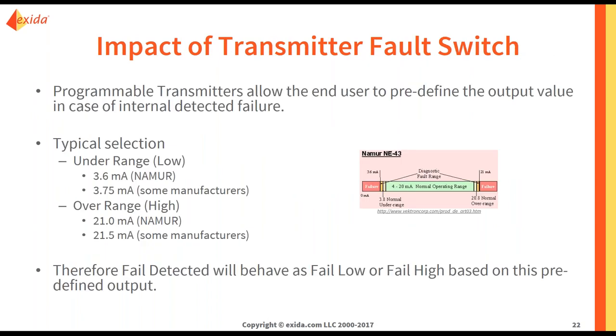Some programmable transmitters allow the end user to pre-define the output value in case of an internal detected failure. You can select if this failure drives the output under range or over range. Therefore, your fail detected failures will behave as your fail low or fail high failures based on this pre-defined output. If you follow the NAMUR standard, under range would be 3.6 mA and over range would be 21.0 mA. However, some manufacturers have it set where under range is 3.75 mA and over range is 21.5 mA, depending on how you configure your system.